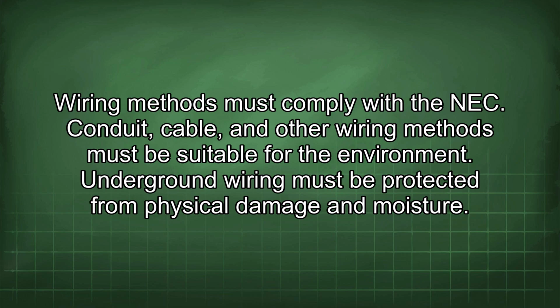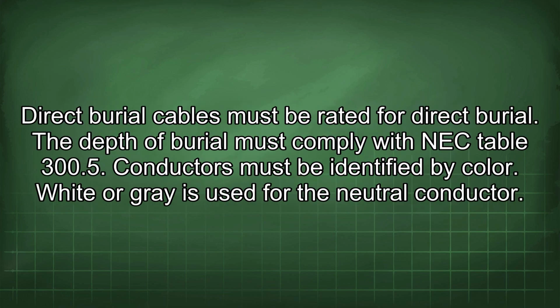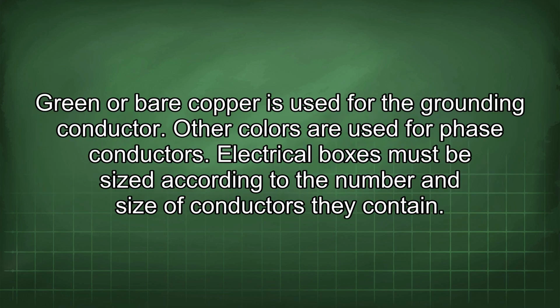Wiring methods must comply with the NEC. Conduit, cable, and other wiring methods must be suitable for the environment. Underground wiring must be protected from physical damage and moisture. Direct burial cables must be rated for direct burial. The depth of burial must comply with NEC Table 300.5. Conductors must be identified by color. White or gray is used for the neutral conductor. Green or bare copper is used for the grounding conductor. Other colors are used for phase conductors.